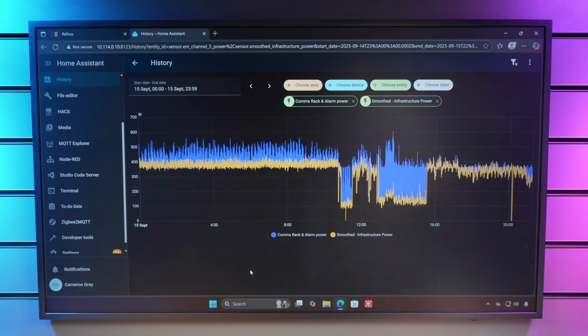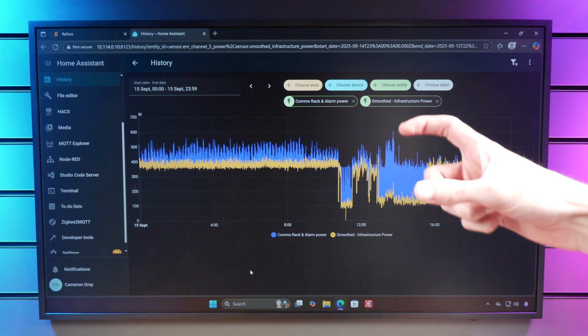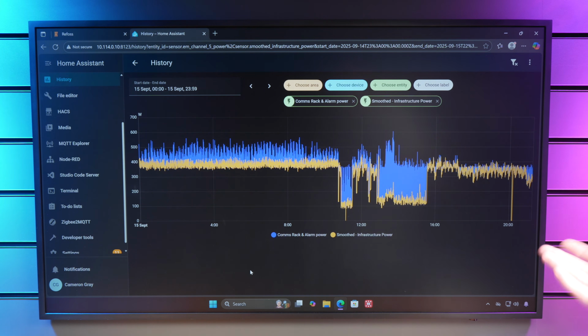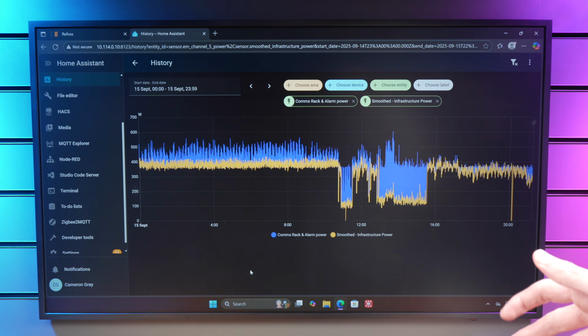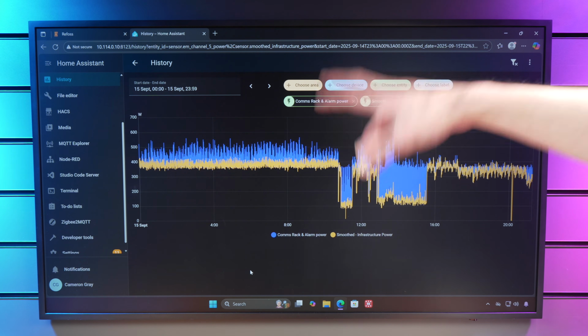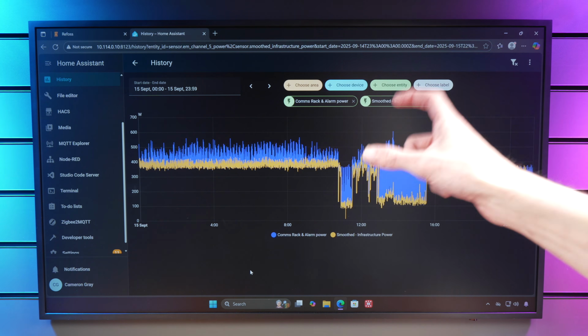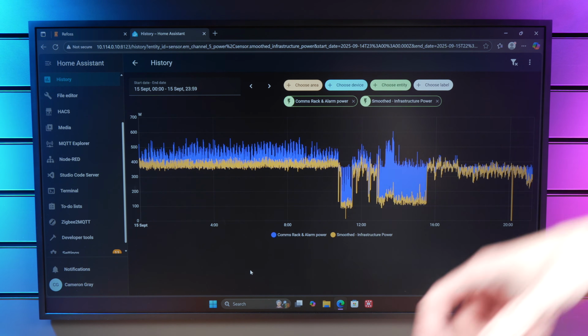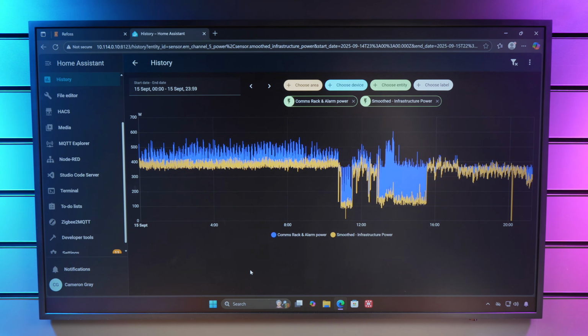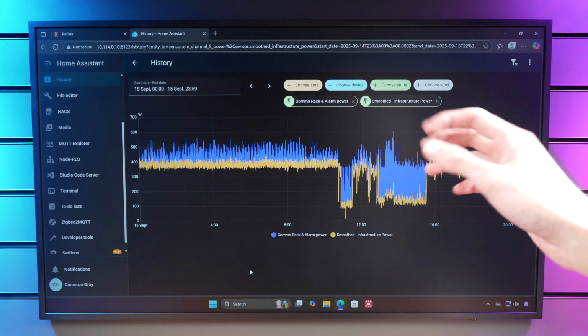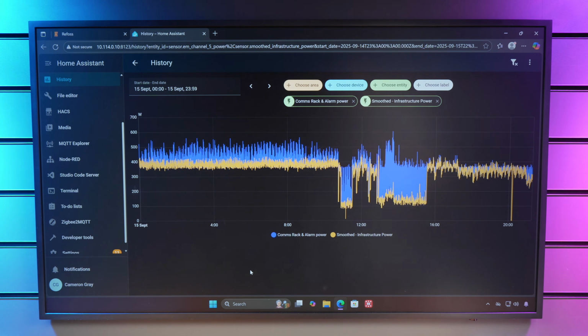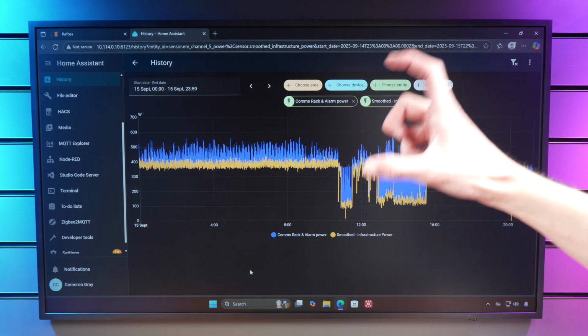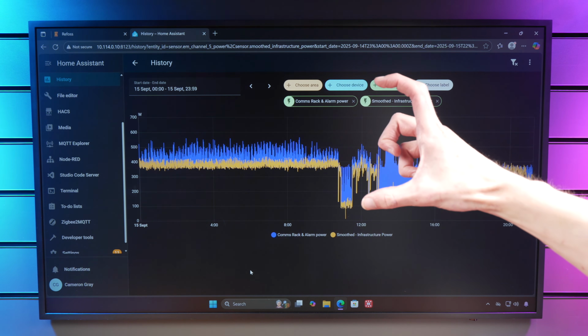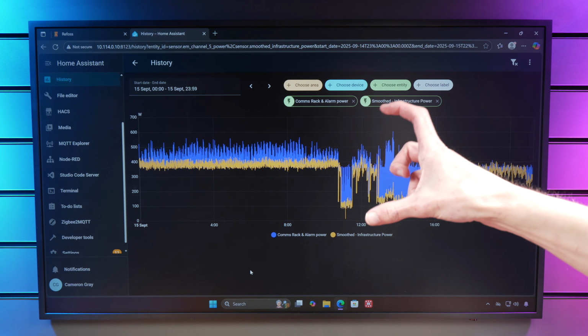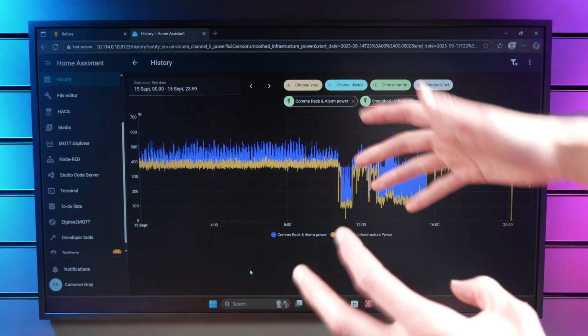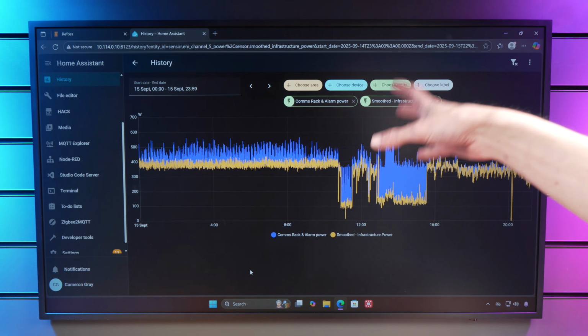When we saw the device earlier, we've got the 3 different phase inputs, A, B and C, and on the device there's 2 pairs of inputs for each phase. You've got A1, A2, B1, B2, C1, C2. Now with these 2 circuits, the comms rack circuit and my socket circuit, those are connected to the same pairs of inputs. The socket circuit is connected to the B1 input and the comms rack circuit is connected to the B2 input. That's where this issue seems to lie: if you've got 2 CTs on the same lettered input and they have wildly different power factors, the power factors interact weirdly and it throws off the readings in this way.